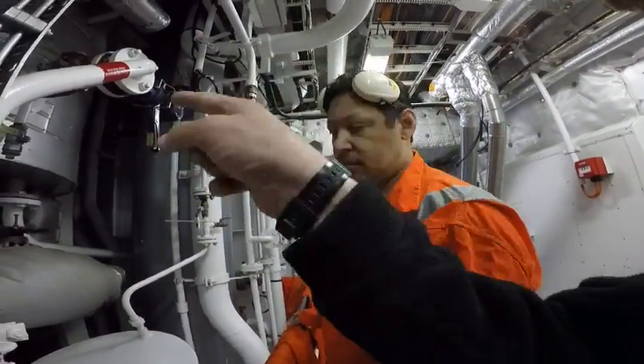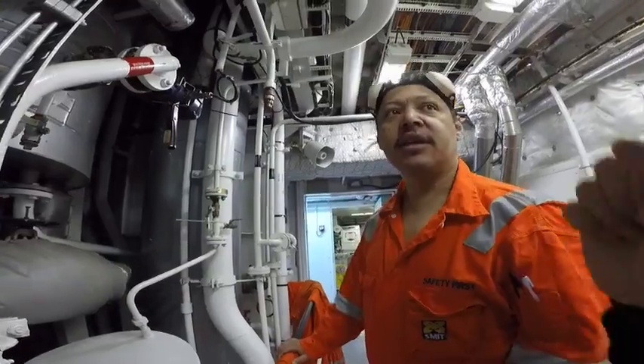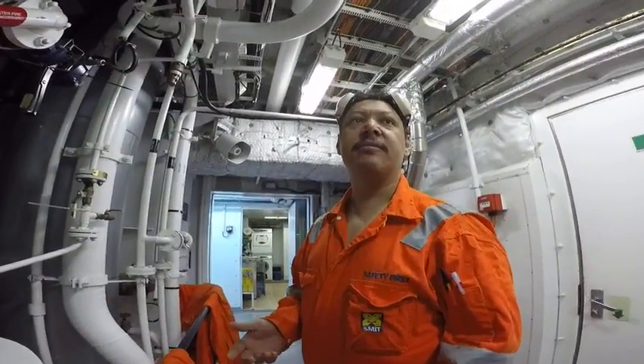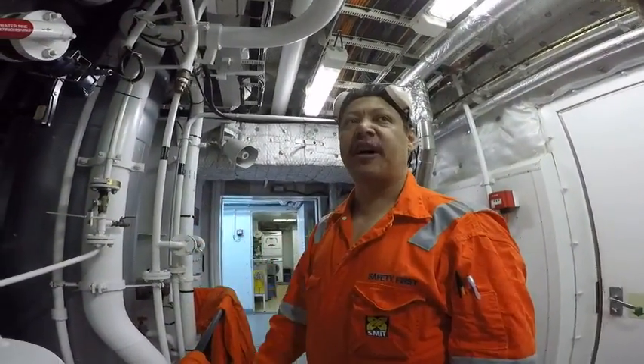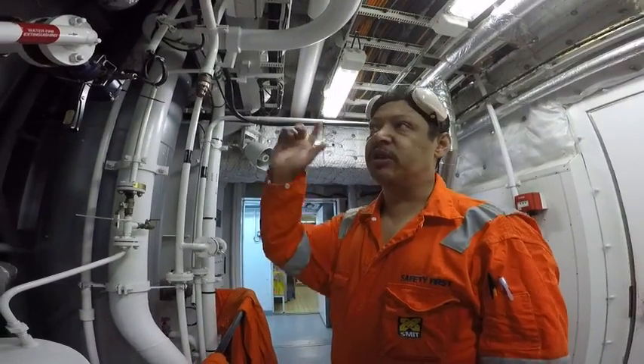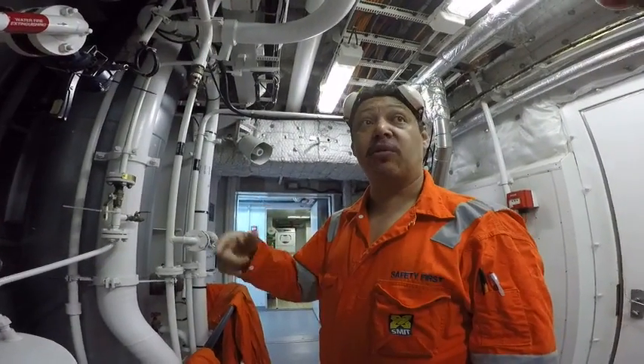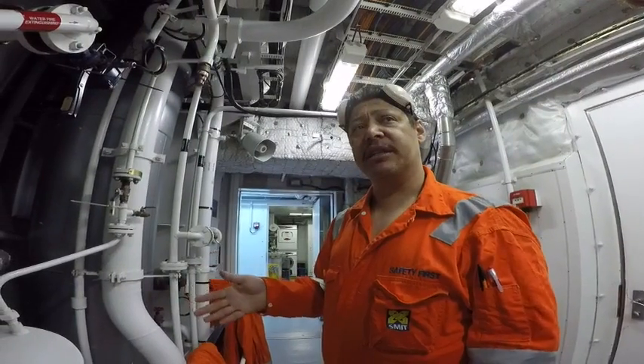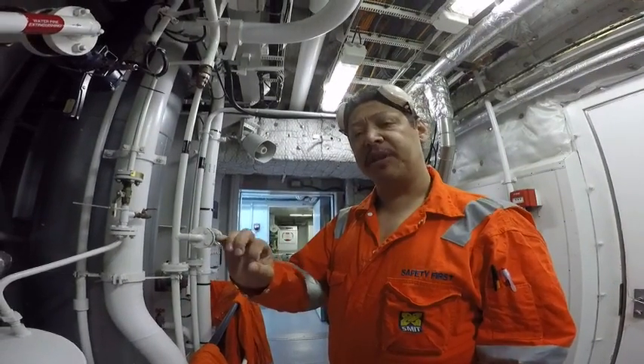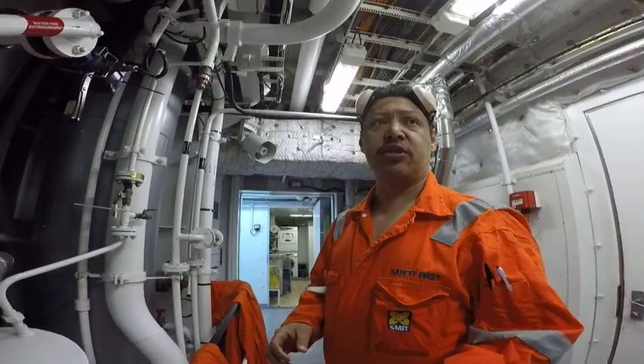And that engine must obviously be running - must it be quite hard? We need the heat and the velocity, lots of it. Normally about 75% load. Because when we do this, we do the turbos as well - the turbine washing, normally about 10 minutes at the predetermined flow rate, and then also your inlet side.